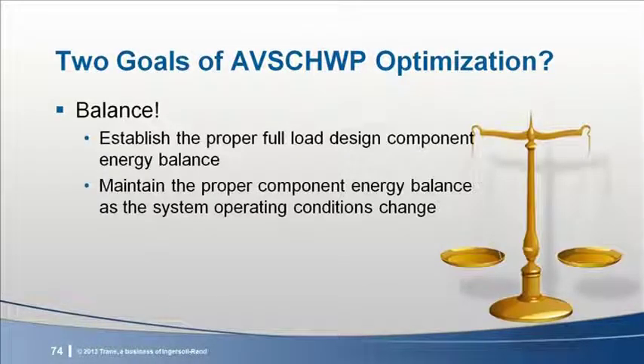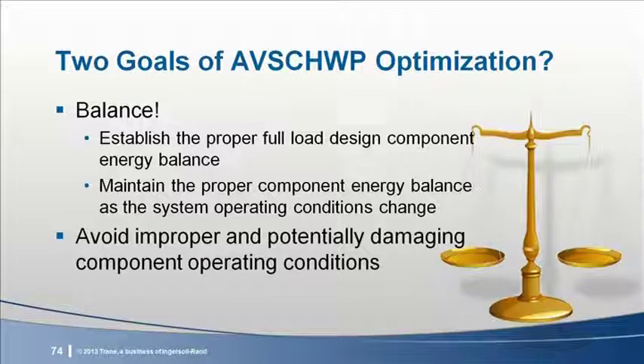As I think you're hearing from this E&L, one thing that has become apparent is that you don't necessarily need a VFD on every motor in the chiller plant to have an efficient plant or to apply some of these control and optimization methods. The first and most important factor of chiller plant operation is balance. As Mick has shown, the system efficiency is greatly influenced by the design conditions. Said another way, if the design conditions are properly balanced, there is much less excess energy to be controlled out of the system. From a control point of view, the ongoing goal is to properly balance the component energy use as the load and operating conditions change.